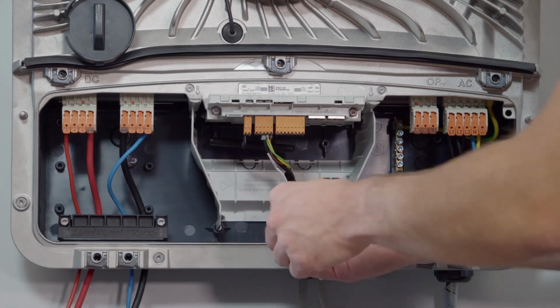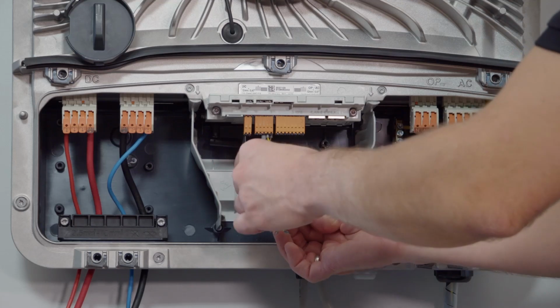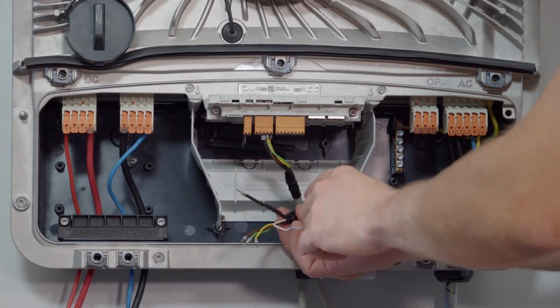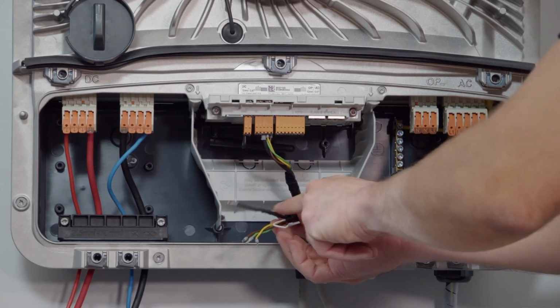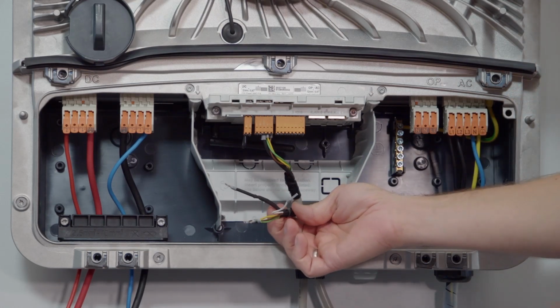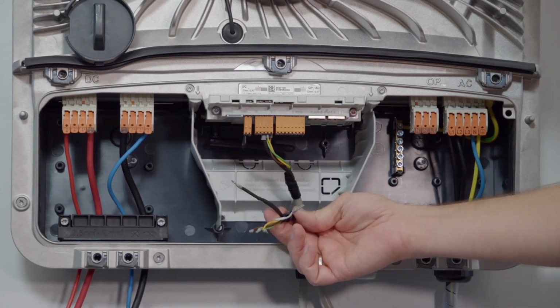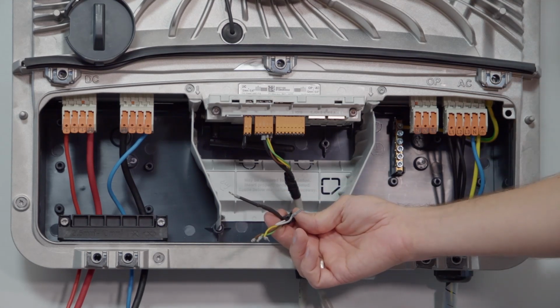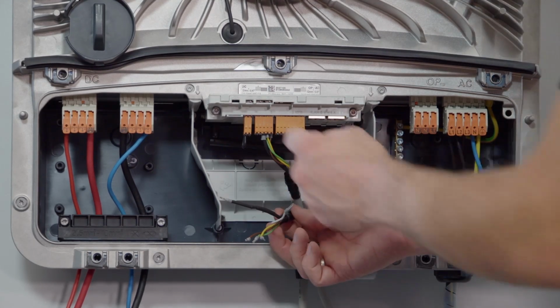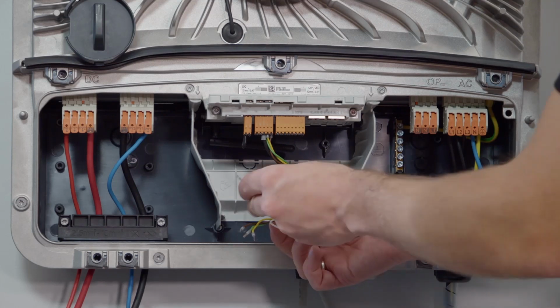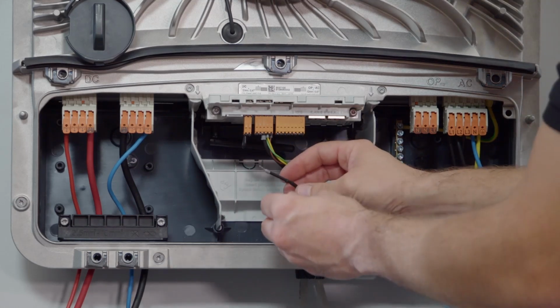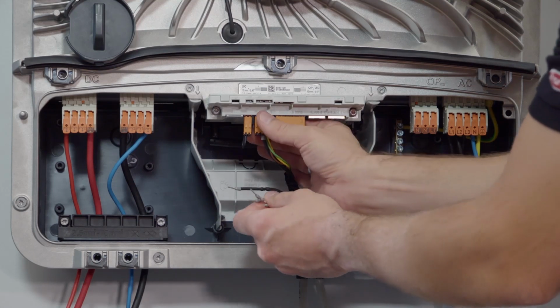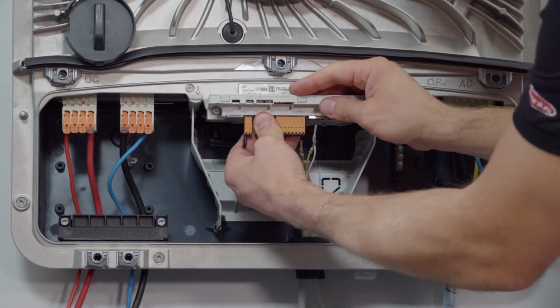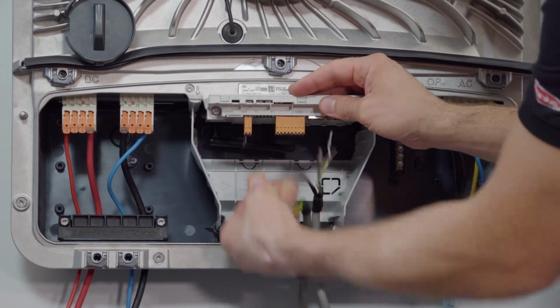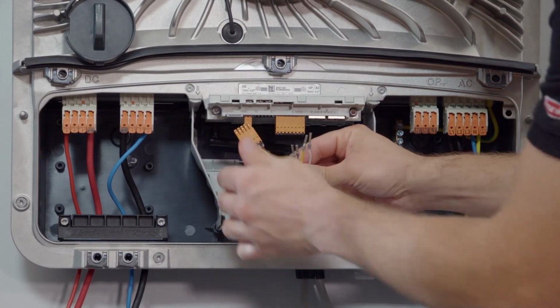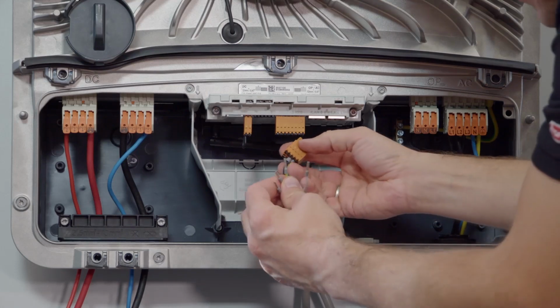inverter and the battery. Please note, and this is really important, especially for the LG battery, we need to unmantle the cover, the shielding of the cable, and bring this shielding to ground potential. And since there is no possibility to do this in the LG battery, we need to do it here in the GEN24 Plus data communication interface. You can see this pin also in the quick commissioning guide, and also we are showing you here in the video.